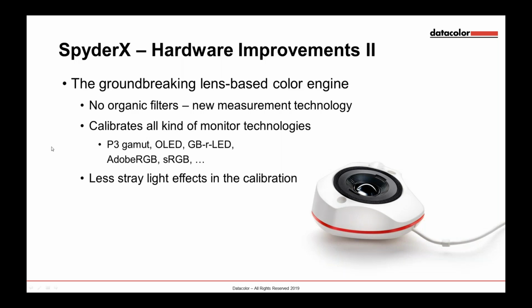And this is all known by the sensor now. So all types of monitors, or modern types of monitors, can be calibrated because the sensor is able to handle the calibration of these new monitor technologies. That's the advantage. And as Oliver mentioned, we have a lens-based system, and the lens gives the possibility to have a focus, and the focus point is not like a honeycomb filter, not defined. Here it is defined, and this gives an advantage regarding stray light effects during the calibration.